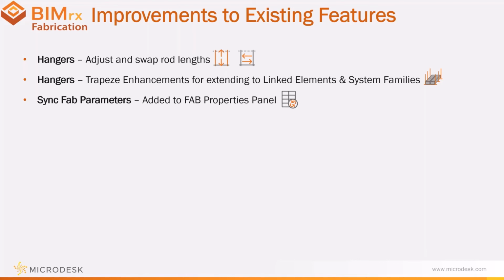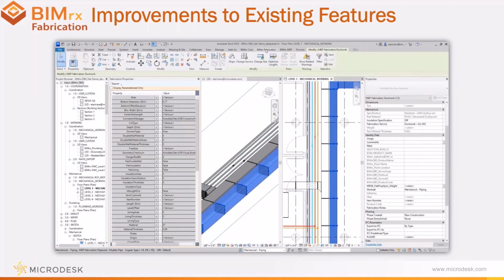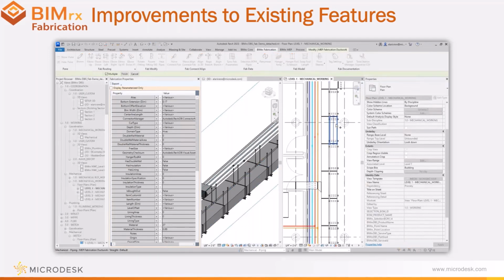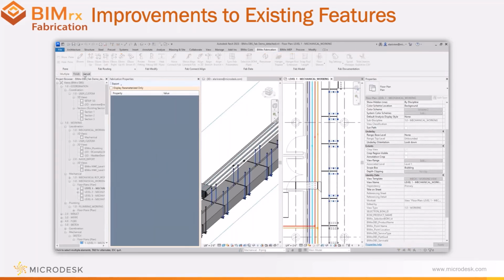Let's take a look. So I am using the standard hanger command to place them down from a configuration that I have already set up. After I place some hangers down, I'm going to use the trapeze command. In this example, I'm going to extend to a linked piece of conduit. This is conduit not within my model. This is conduit from within an electrical model. I'd like to note that this command also allows for multiple selection of elements to avoid. If you have a model you want to work on, and then other models, we can do that.